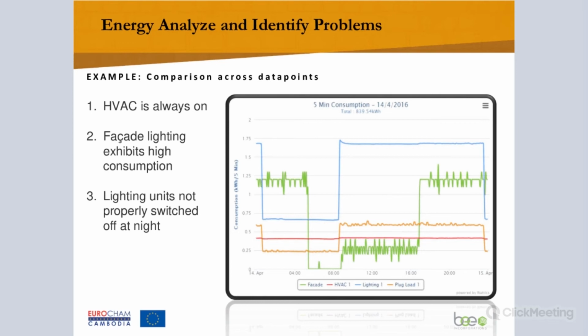You can see here that the lighting units were not properly switched off, because the line doesn't go to zero. You can look into where lighting electricity is still used. Maybe there are some lights, like emergency lights, that must stay on, but it also looks like in this case people simply forgot to switch them off.